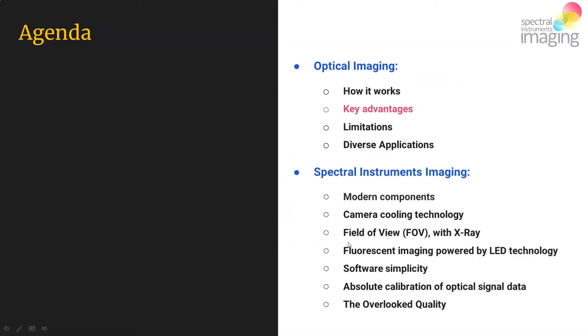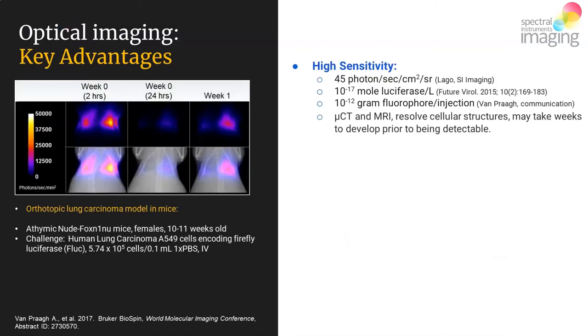Now we're going to transition and discuss the key unique advantages of in vivo optical imaging. Top of the list is that optical imaging is incredibly sensitive. There are devices — including those from SI Imaging — that have very high sensitivities, getting down to 45 photons per second per centimeter squared per steradian. This can translate to very low copy numbers of luciferase enzymes and fluorophores needing to be injected in order to achieve detection.